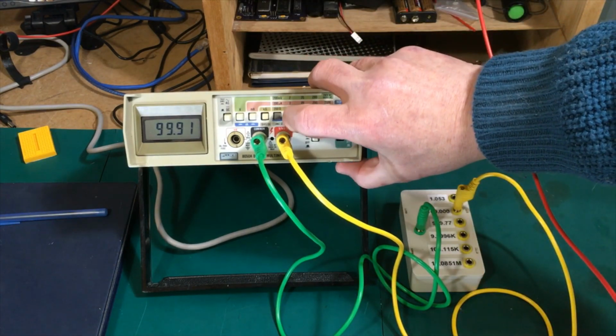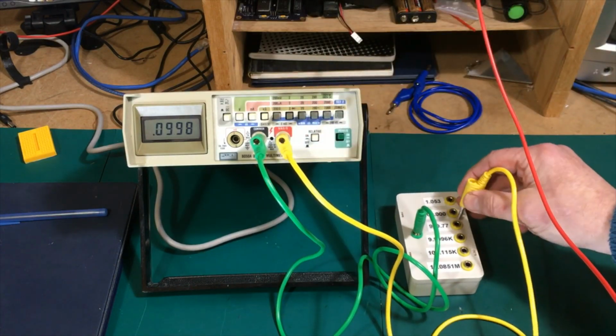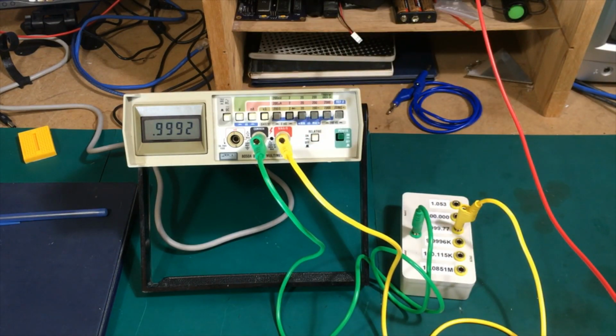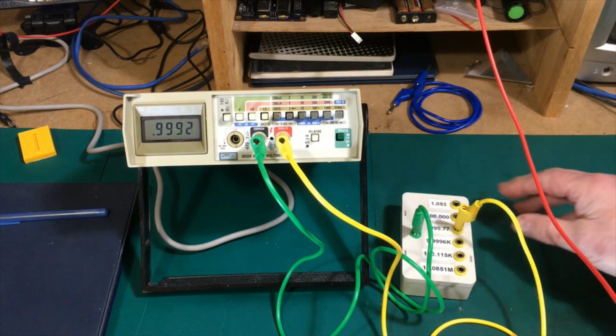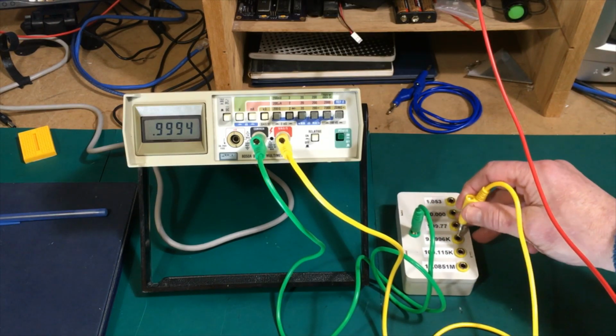Now we're going to go up to the next range on it, the 2K range. We'll measure this resistor. Now this should come in between 0.9986K and 1.0010. So yeah, we're right in the middle of that range too. So far this meter is looking fantastic for a meter that's old enough to be a father itself. It's doing pretty good. This one should be between 9.993K and 10.007K. We're down near the lower end of that, but I'm happy with that. That's good.